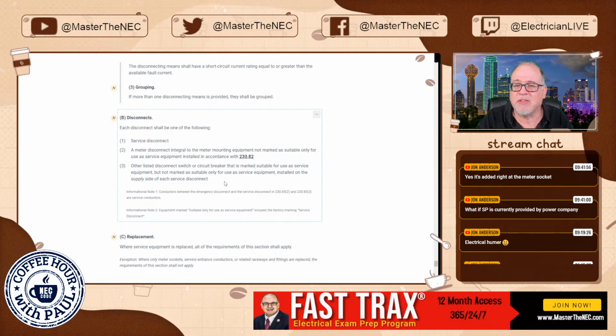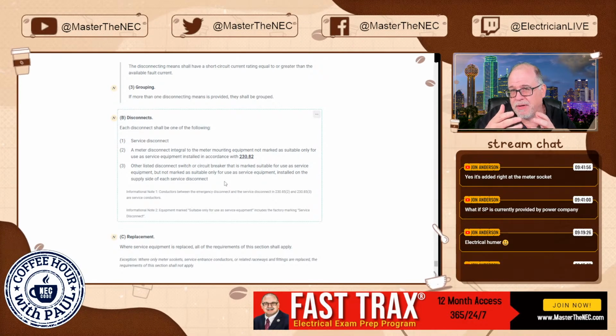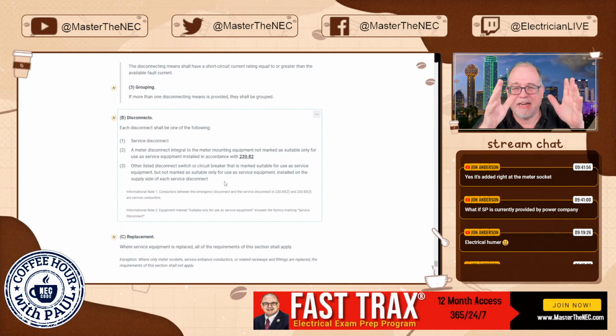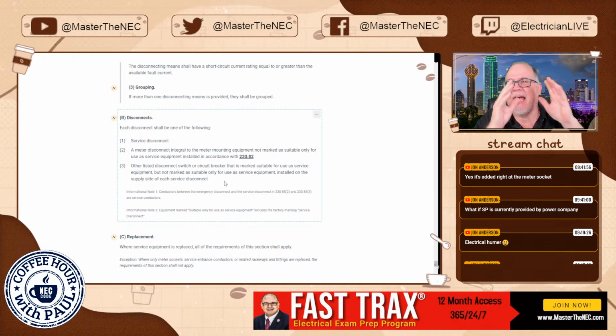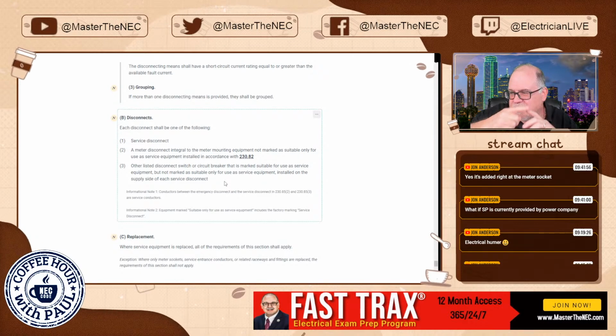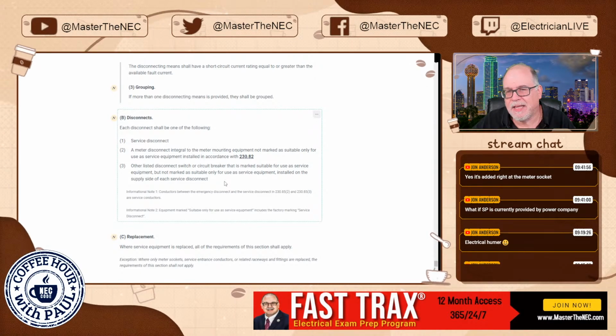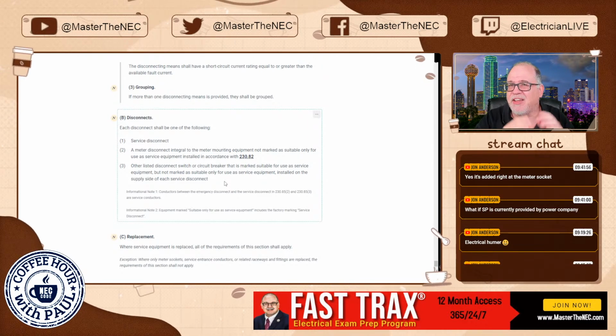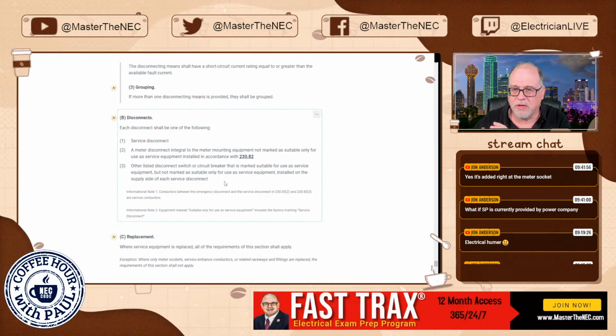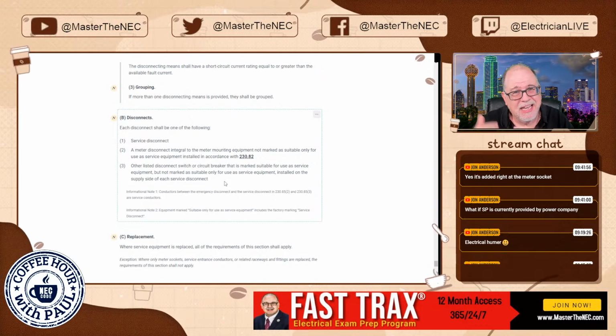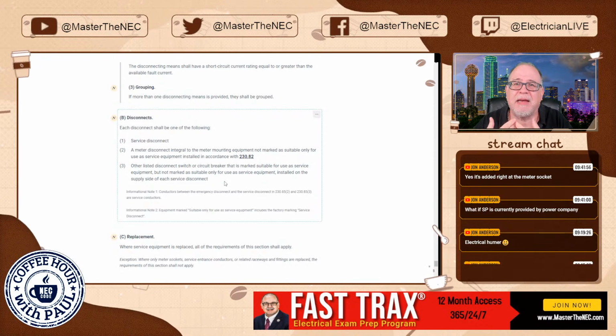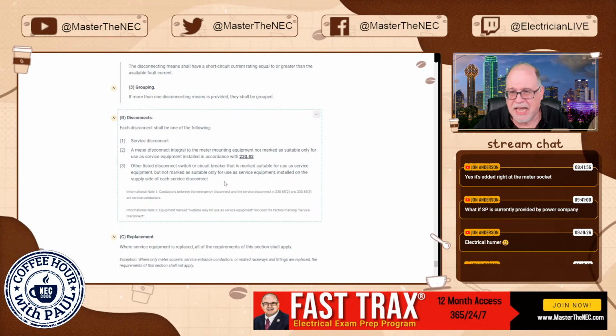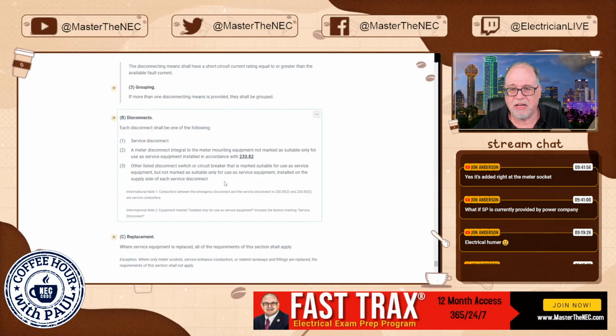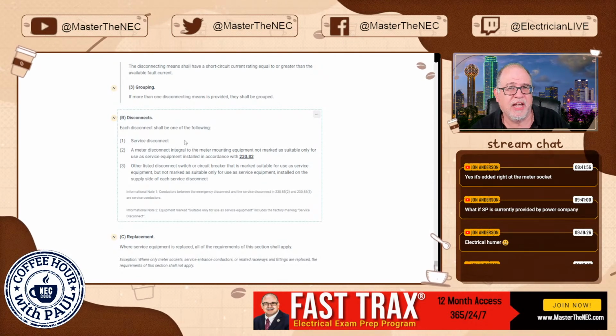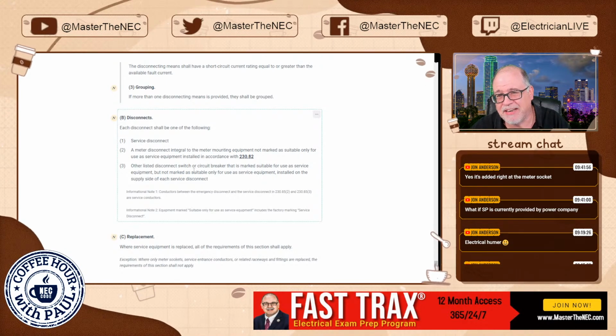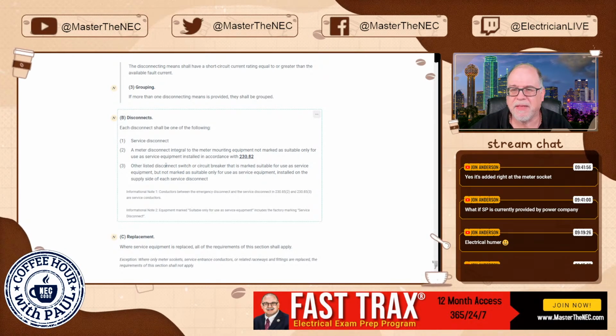The difference being that with the service disconnect on the outside, if you happen to put a disconnect means, and we'll see that in a second in item number 3, but if you happen to put a disconnect out there and you continued on into the dwelling, then the difference here is that meter disconnect doesn't change the fact that those are still service conductors, okay? And so you have to be careful with that. And you still have to meet all the same rules that you have in 230.70(A)(1), outside or nearest point of entry, okay? It doesn't change it. Now, where the service disconnect would change that, because then they'd be feeders as they leave that service disconnect. Subtle points, but keep that in mind.